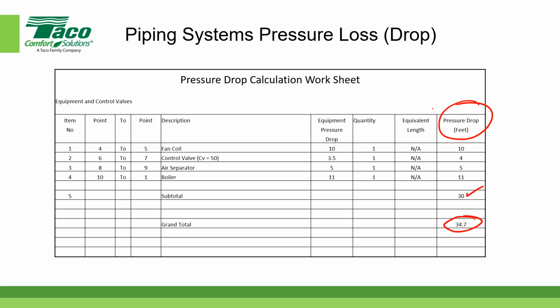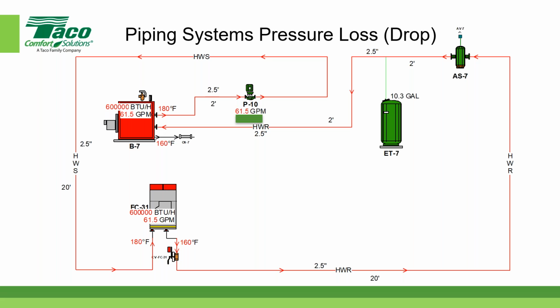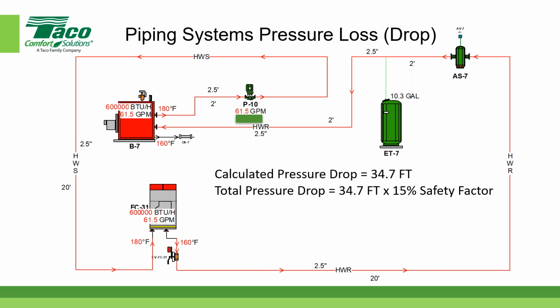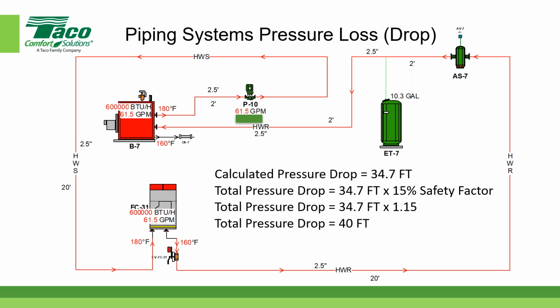So let's see what the computer calculated. We did this manually, and we did this using the HSS software. And if we take that little green tab away, drum roll please, Brett. 34.7 feet is the calculated total pressure drop. With a safety factor of 1.15, the total pressure drop is approximately 40 feet, and we're going to select the pump in a minute at 65 gallons per minute at 40 feet. But before we get into that selection, there's that value of 34.7 feet before we add the safety factor in there.